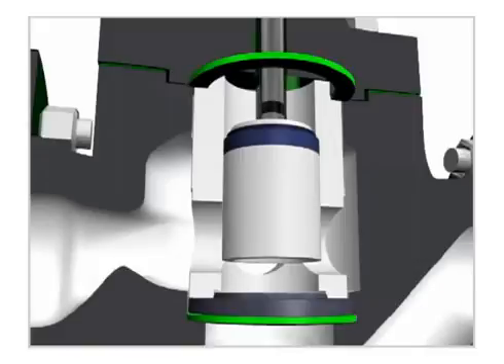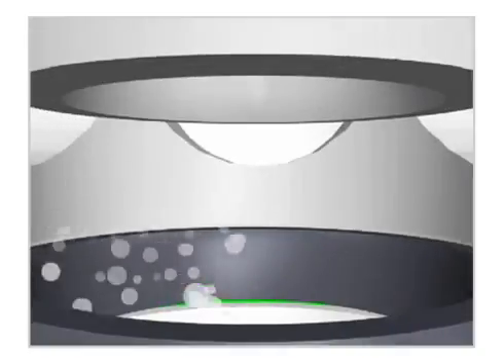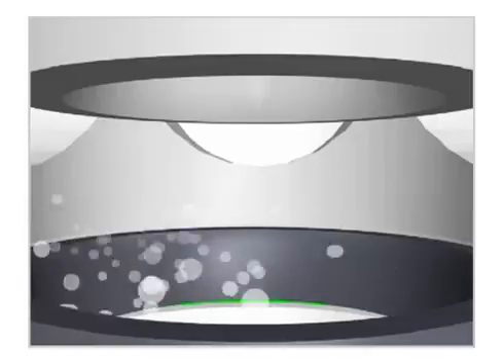The point of maximum velocity and minimum pressure is called the vena contracta. Vapor bubbles form in the liquid when the pressure falls to near the level of the liquid's vapor pressure.